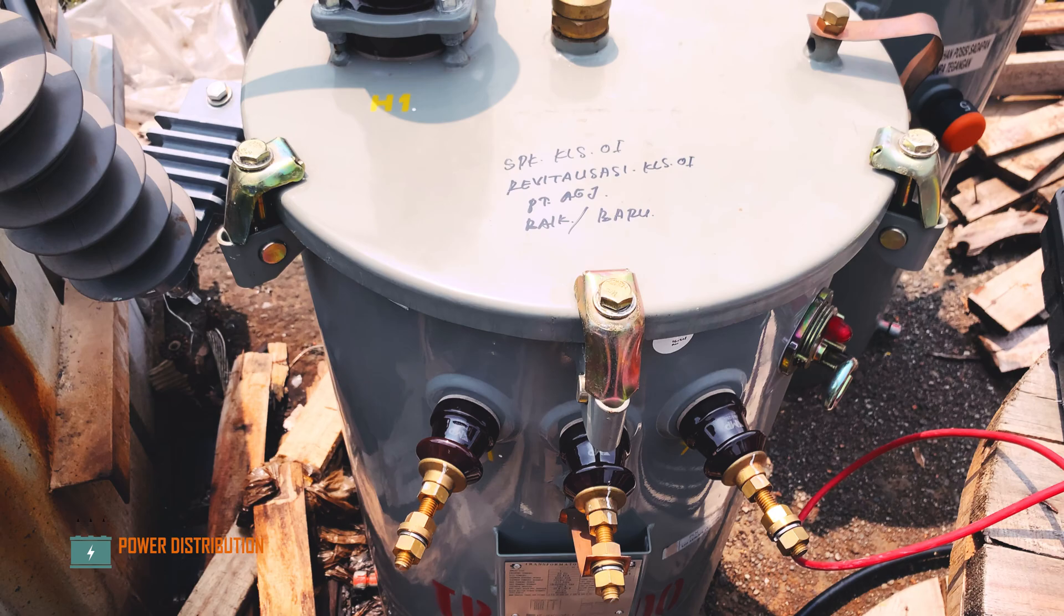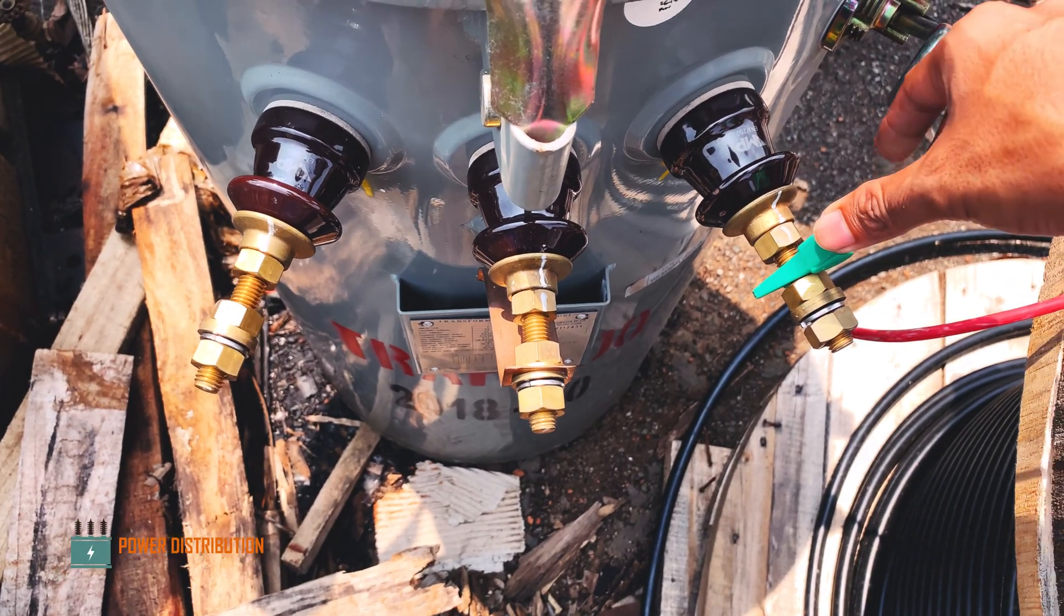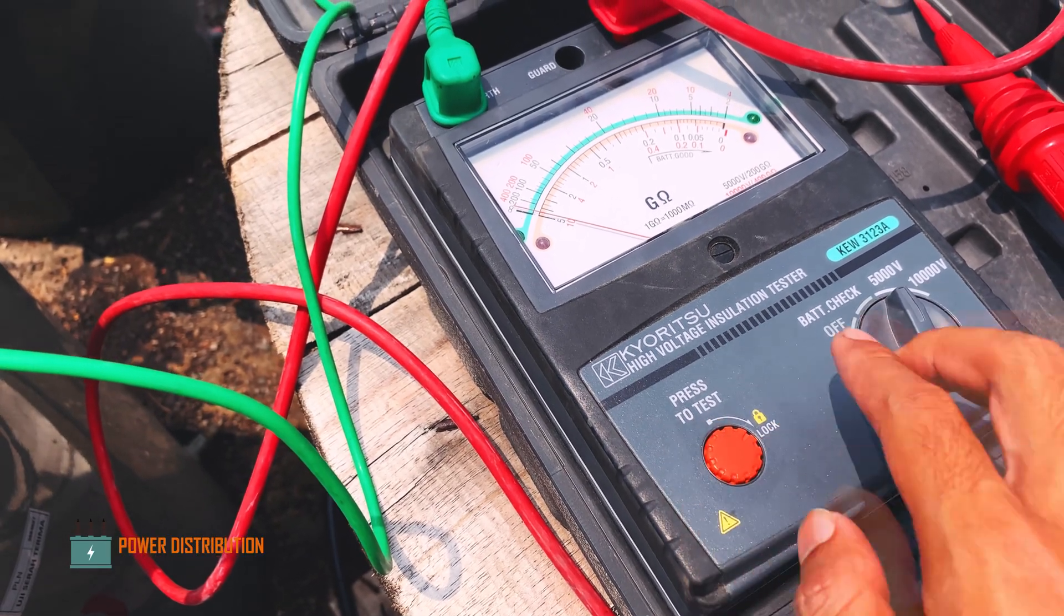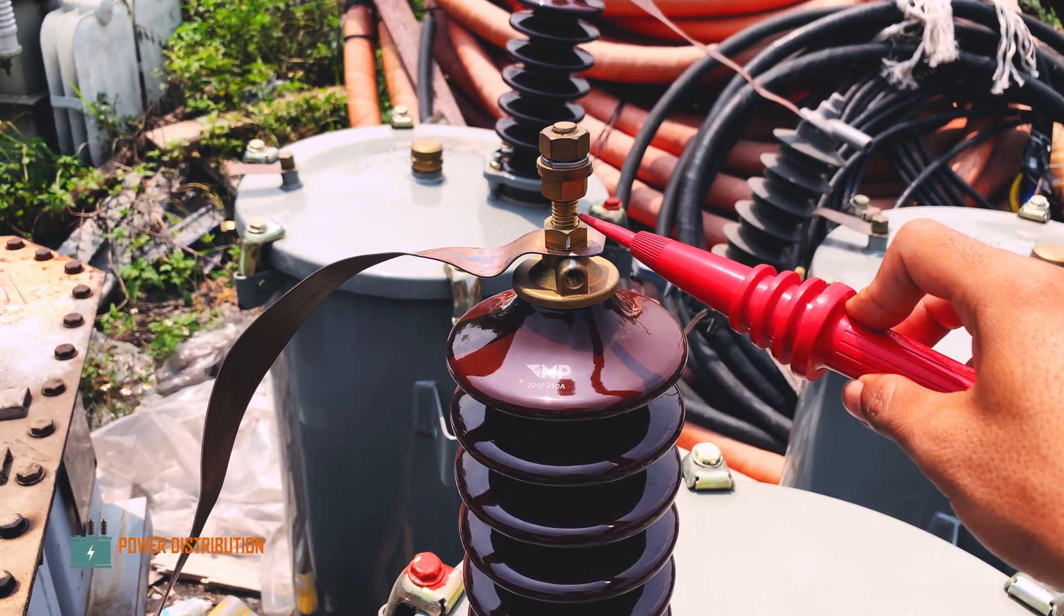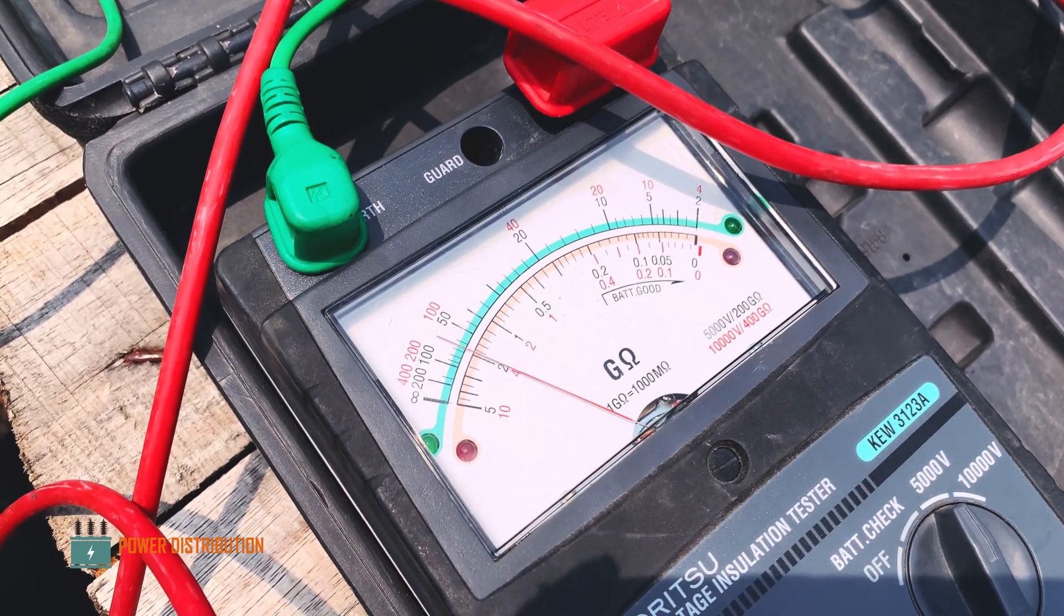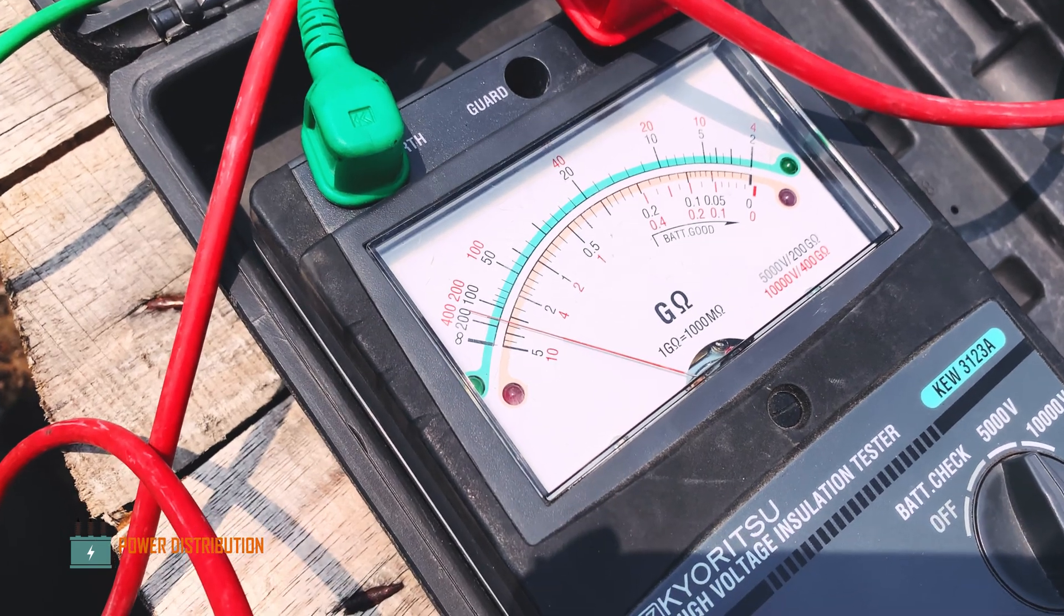Just for the sake of comparison, we will measure the resistance of this brand new three secondary bushing transformer. Again, the primary bushing... as you see, it shows a fair reading. It's a brand new transformer. Wait for around one minute. As you can see, it passes around 160 gigaohms, which is very good.